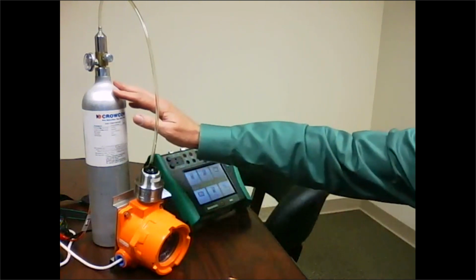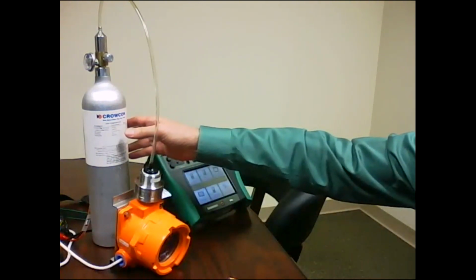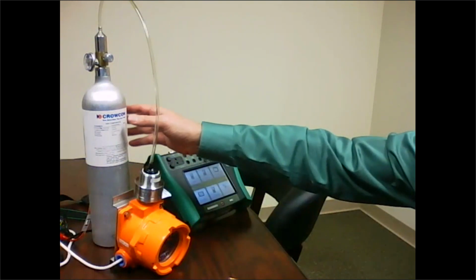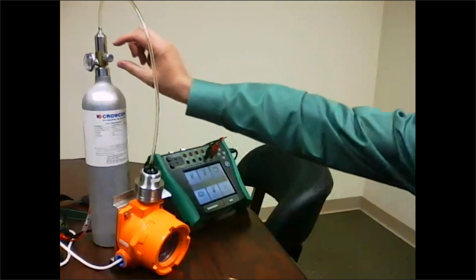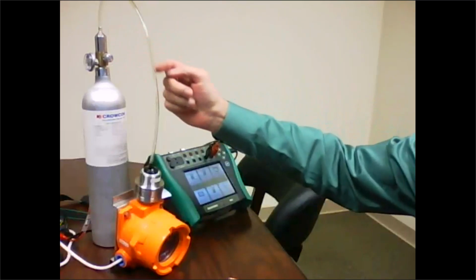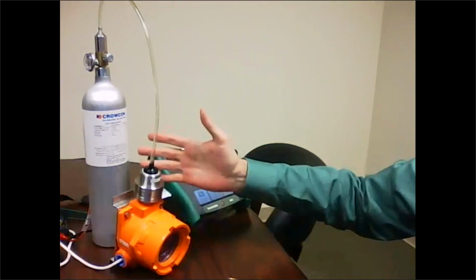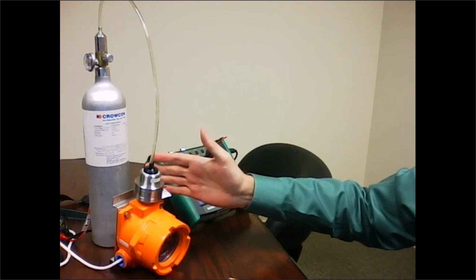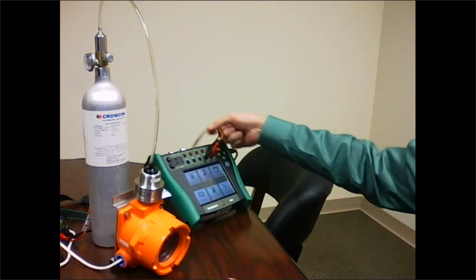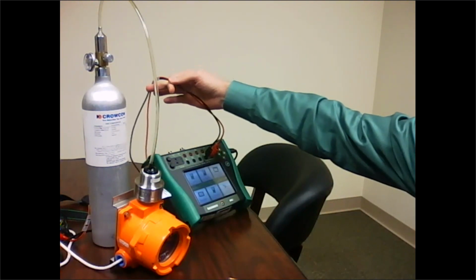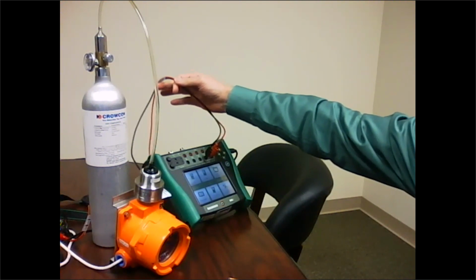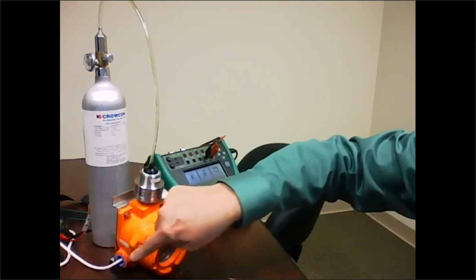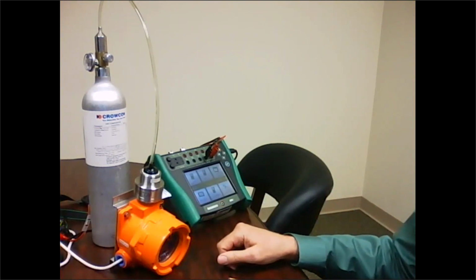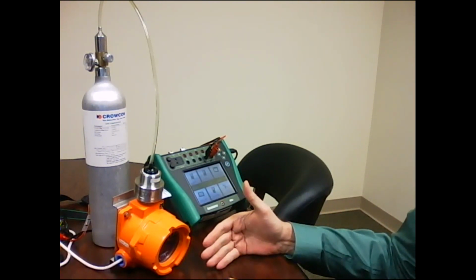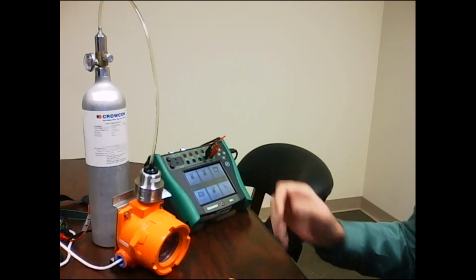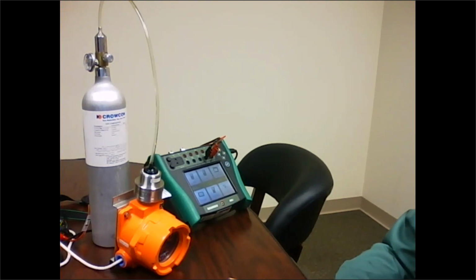And then here's the sample bottle. So this has 50% LEL methane as our standard. So when I turn on the regulator here, I'll expose the sensor to 50%. And then here's my calibrator, and just like Roy mentioned, I've got 2 leads here measuring the milliamps, and you can see the white cable sneaking around inside the transmitter. So I'm measuring the 4 to 20 with my calibrator.